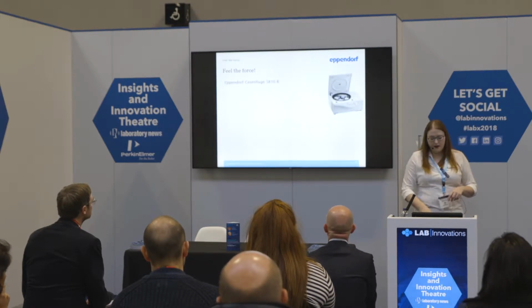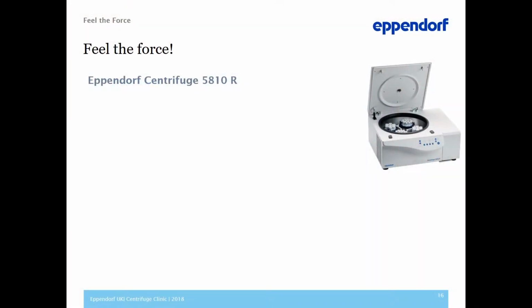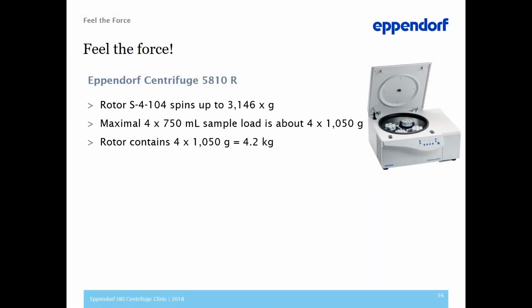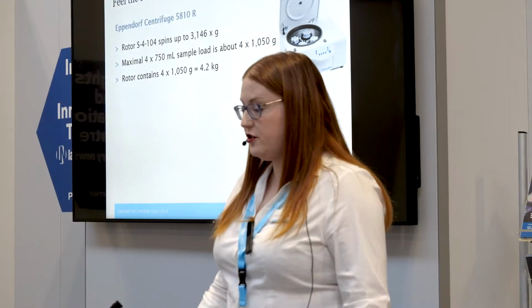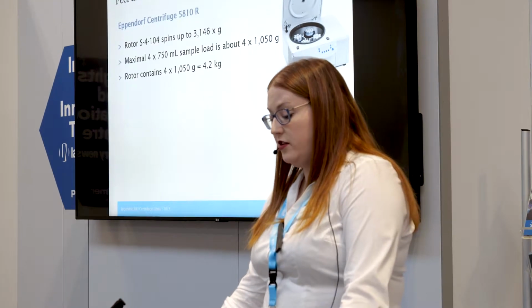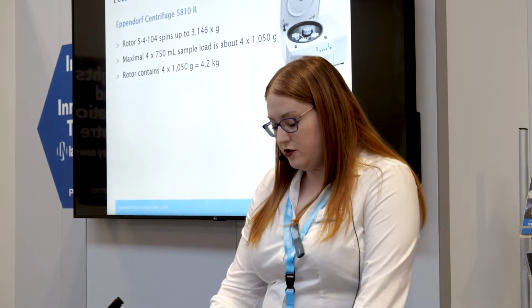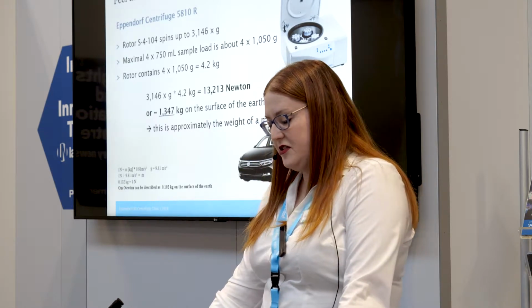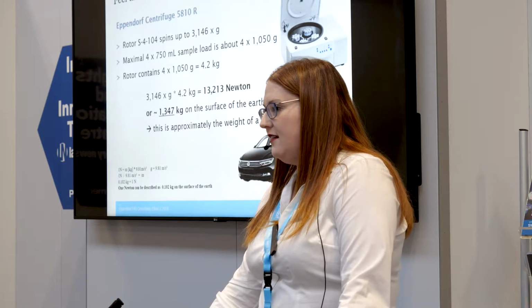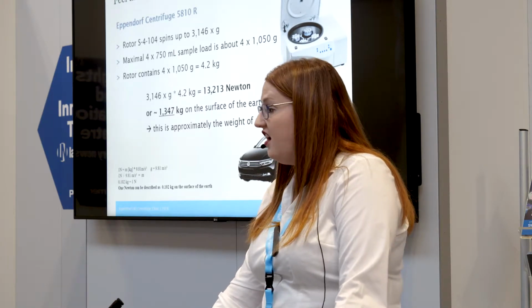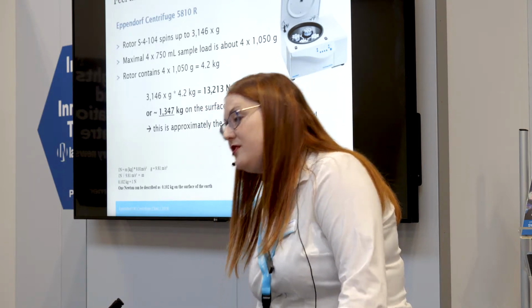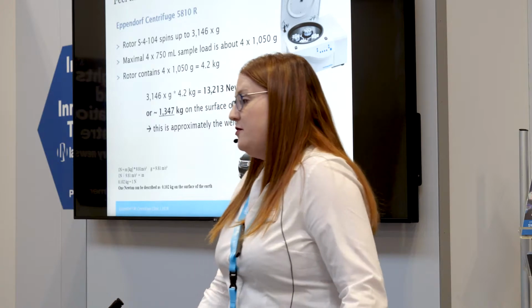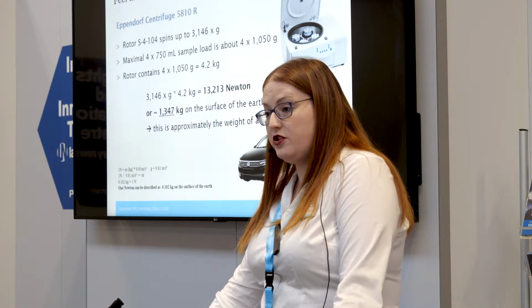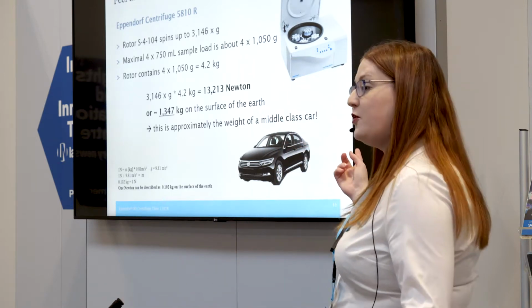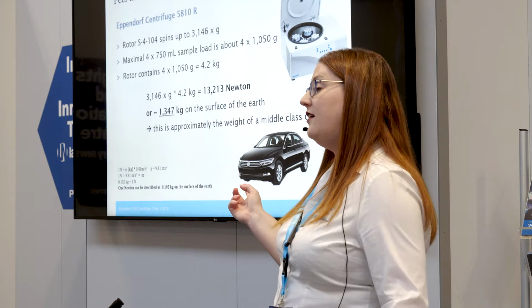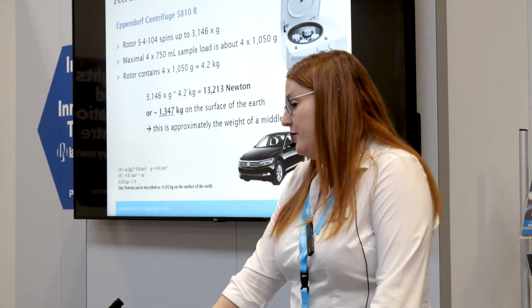So, this is our most popular model of benchtop centrifuge. It has a maximum capacity of 3 litres. The rotor, the S4104, can spin up to just over 3,000 G. This one takes 750 mils. So, doing the maths, that means that once it's spinning, the relative weight is basically the same as a car. This is why earlier we were talking about how important it is for centrifuges to be used correctly and for them to have all the safety precautions that mean that if there was a crash, it's contained, because you don't want these sorts of forces being let loose in the lab. And that's why, in the example I mentioned earlier, that rotor took out 2 other centrifuges and a wall.